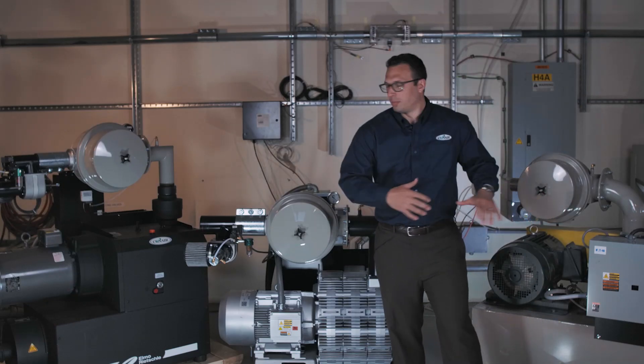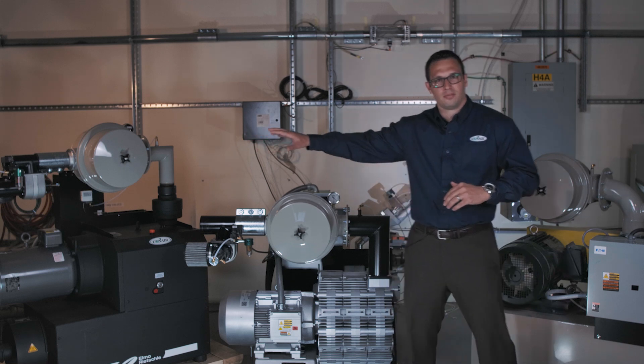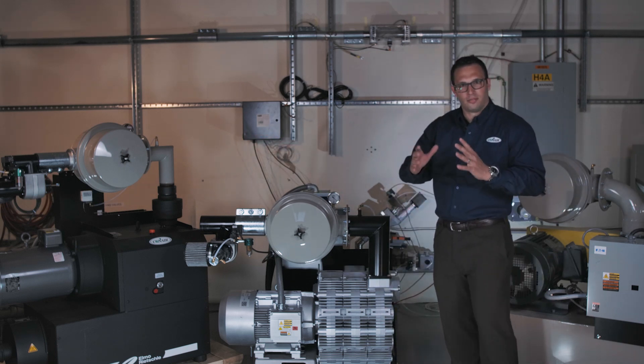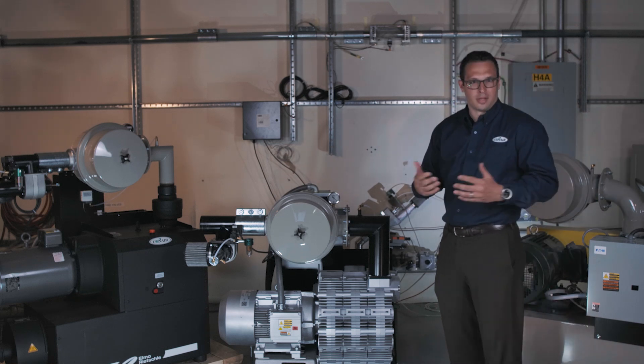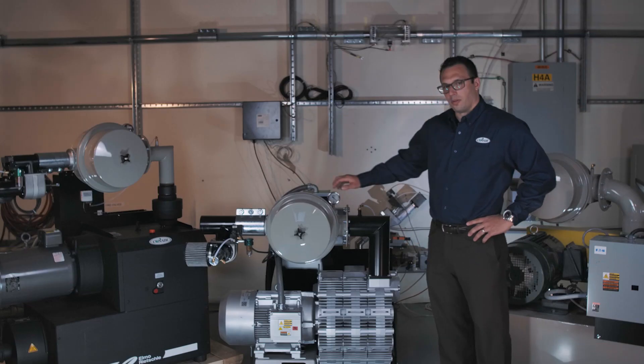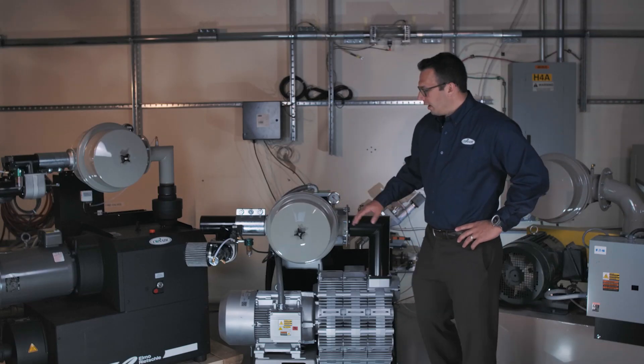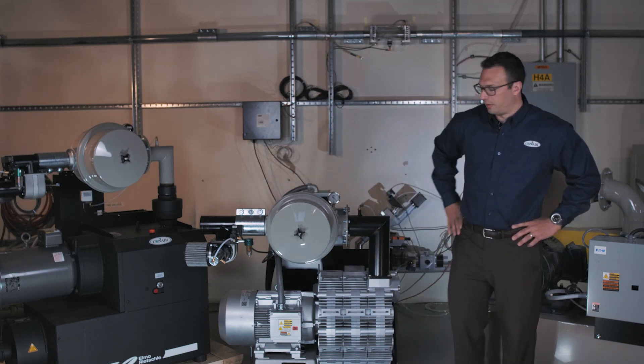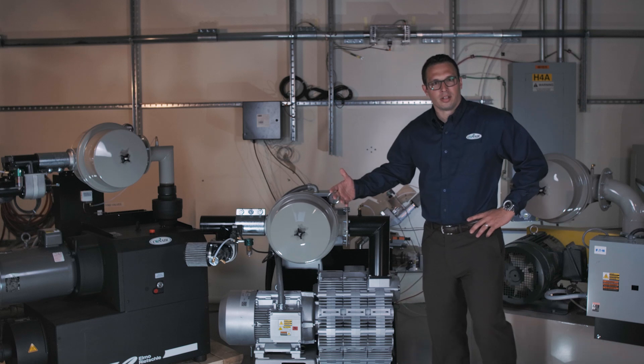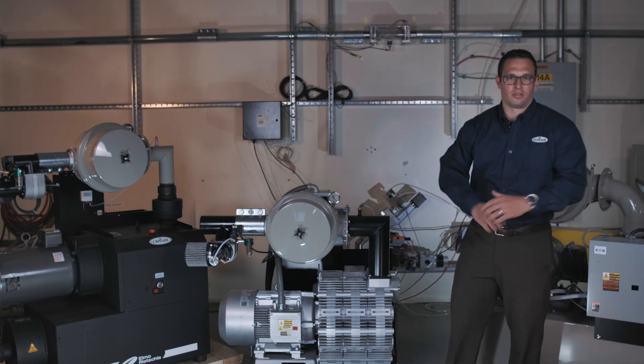Let's talk through the Conair HRG pump. We call it the HRG pump because it's a hybrid regenerative pump. We talked about the capabilities of the positive displacement all the way up through the LDP family, and now this hybrid is going to fit right in between the two to fit that much needed gap with respect to vacuum capability. The HRG pump comes with a safety filter standard. It also comes with a vacuum gauge for quick reference. And also notice we have over here a breaker valve, and this is the idle mode valve, as we call it, to allow the pump to break into idle when all of your receivers are satisfied on your vacuum line.